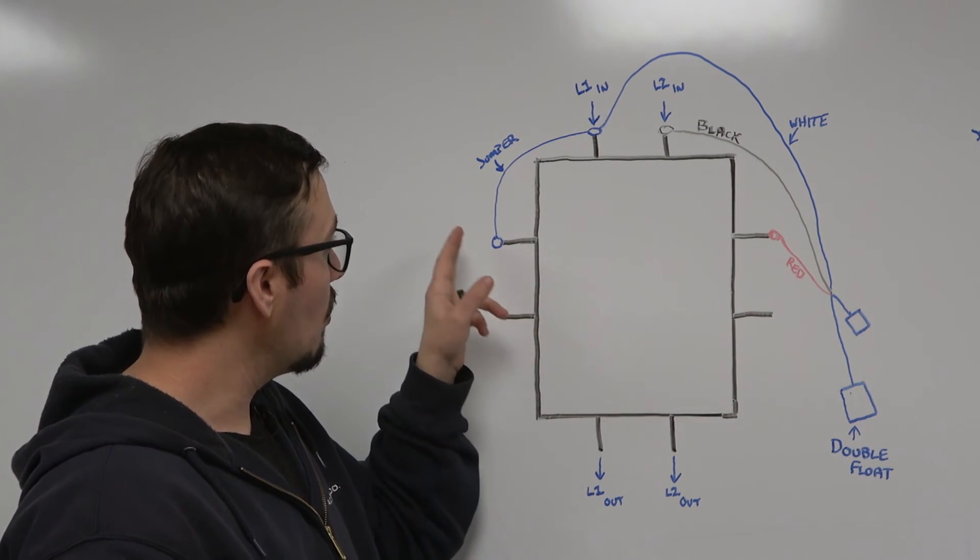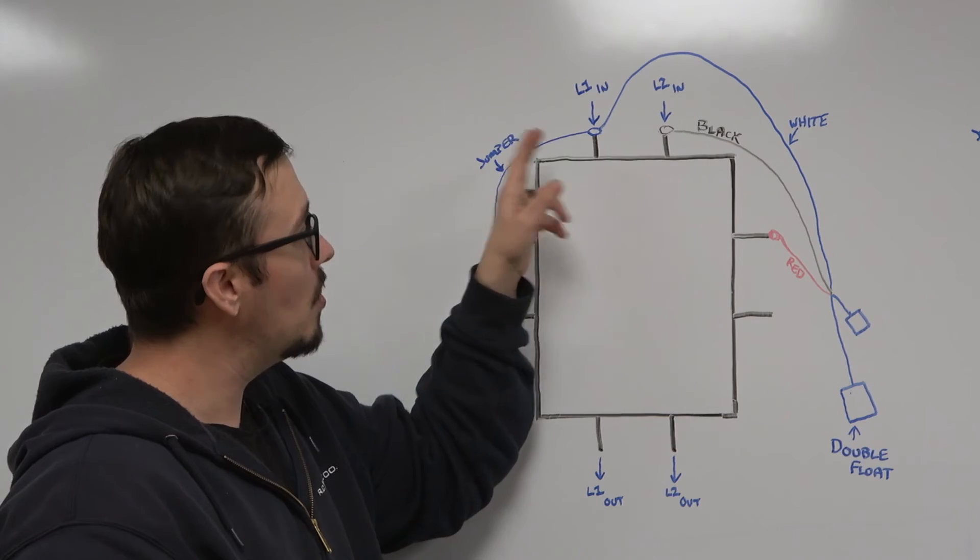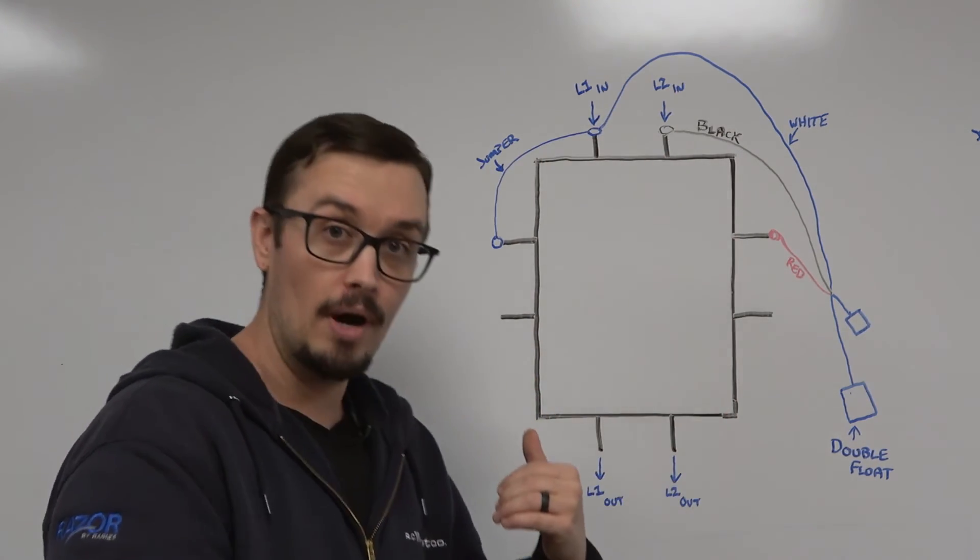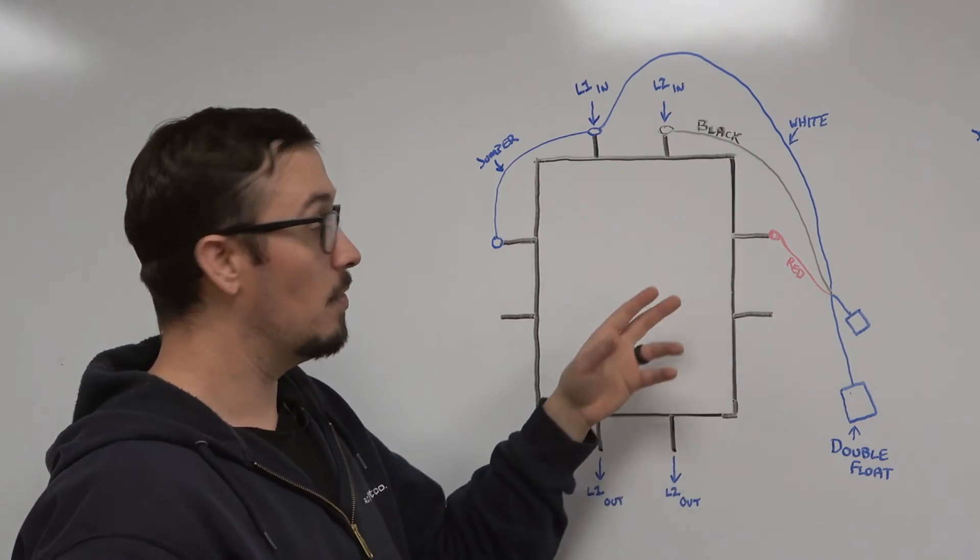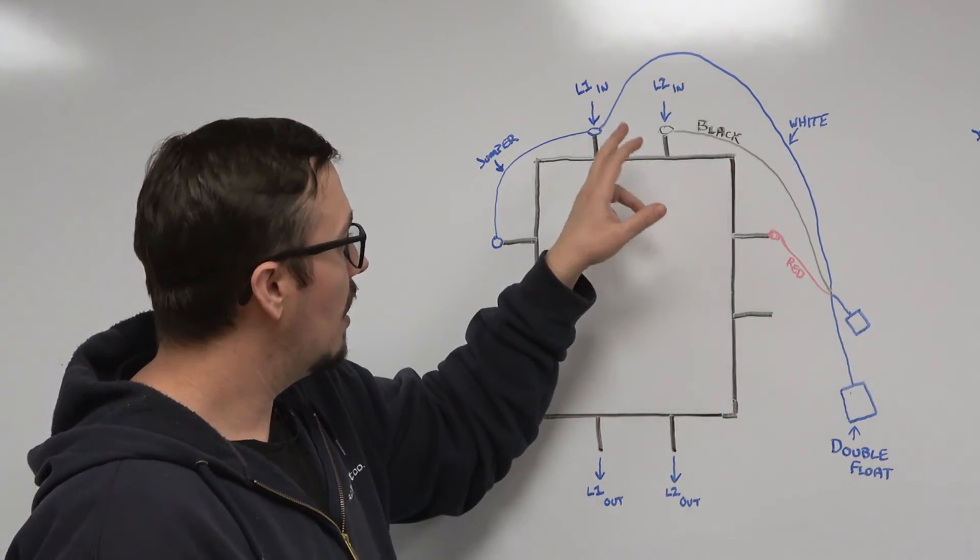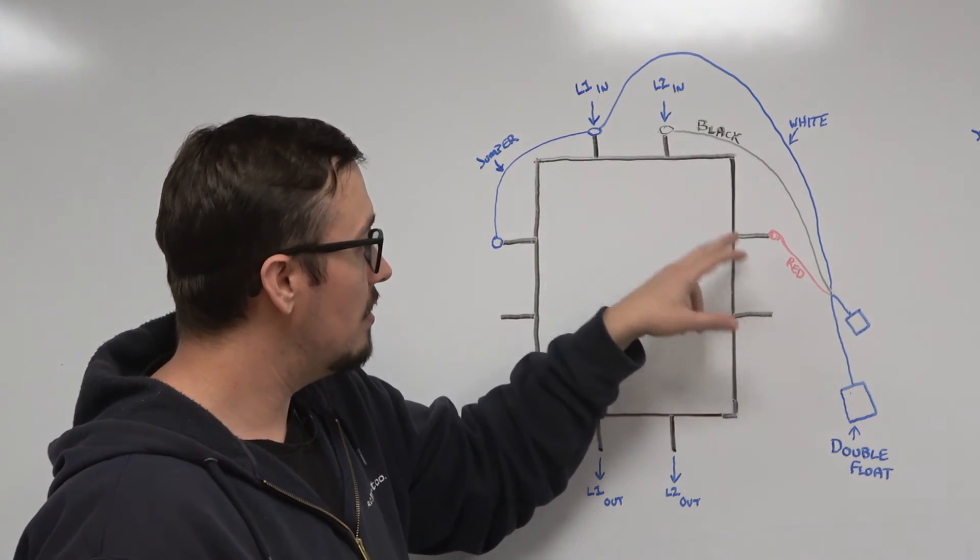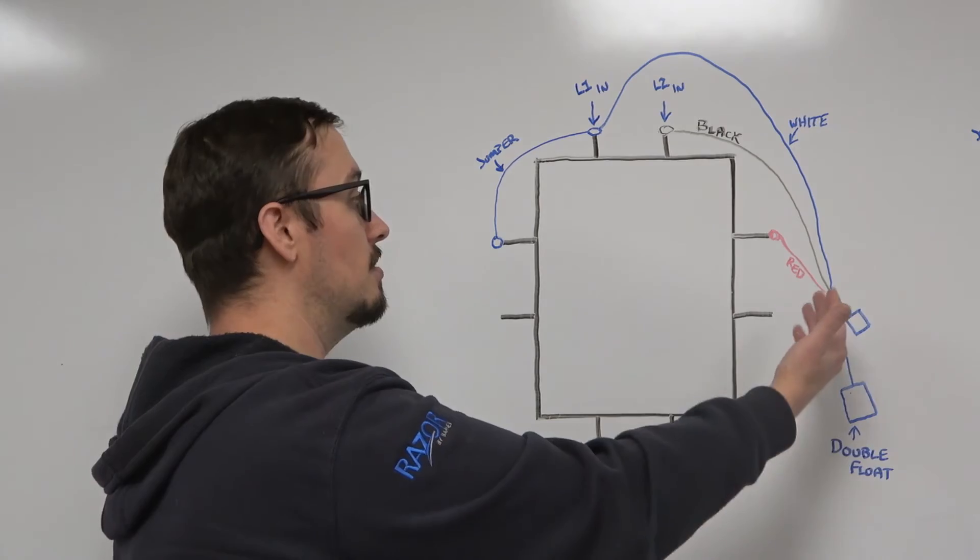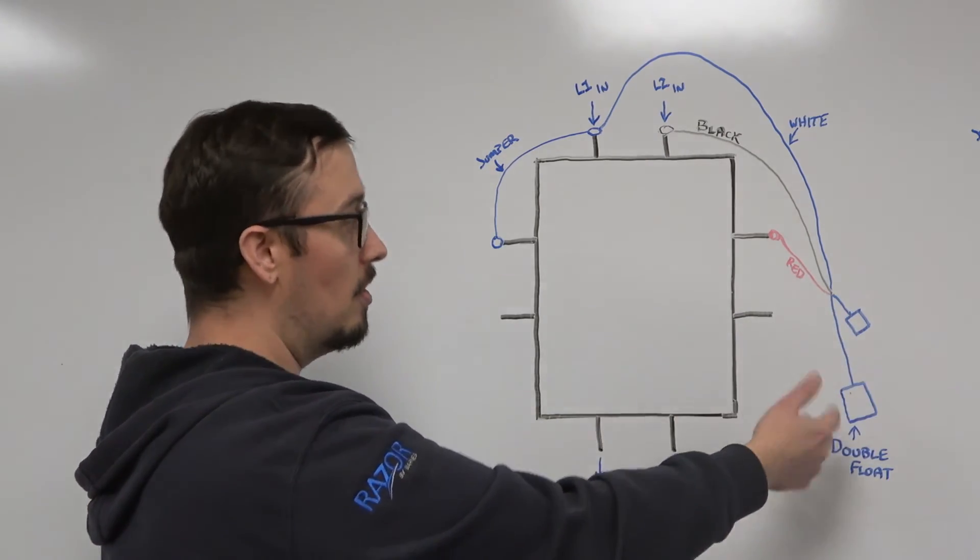In this configuration it's a little bit different. We're jumpering our coil over to L1, but we're also jumpering our white wire, which is the coil wire or the power wire essentially for the coil in the relay. Then we've got our black and our red jumper between, so it goes through the float switches.